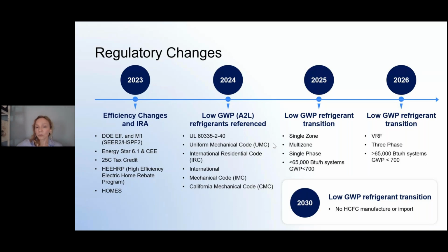In preparation for the refrigerant transition, the UL standard 60335-2-40, which regulates primarily safety features of HVAC systems, incorporated A2L, our new class of lower GWP refrigerants. That then filtered down into the other codes, including the Uniform Mechanical Code, International Residential Code, International Mechanical Code, and California's Mechanical Code.